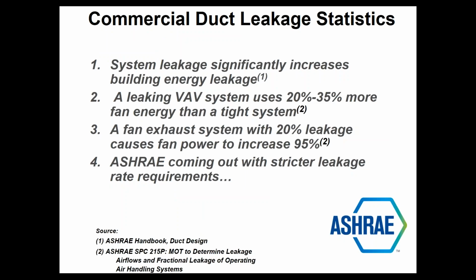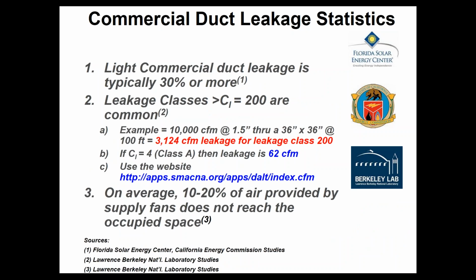Duct leakage, I'll spare you the statistics on how bad and how leaky ducts are. I'll just say they're really, really bad. A lot of these systems are leaking 1/3 of their air into unconditioned spaces. It's very common for both supply systems as well as exhaust systems. Really bad, especially if they have shaft exhaust that's not fully ducted, right? So there are requirements in the code to get some of these spaces to leak less duct leakage, which means less fan energy involved and perhaps even less heating and cooling waste.